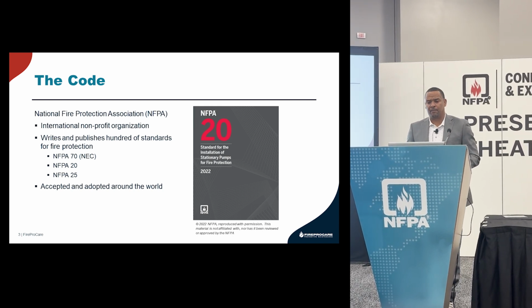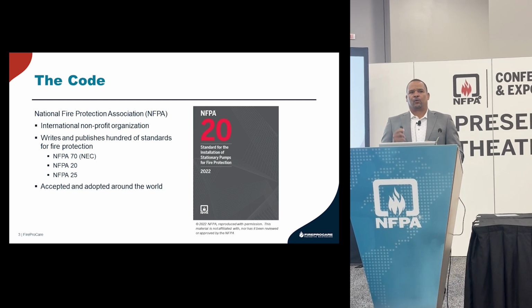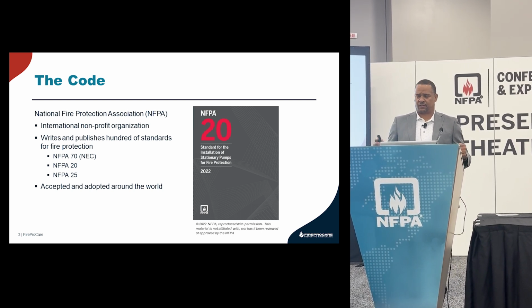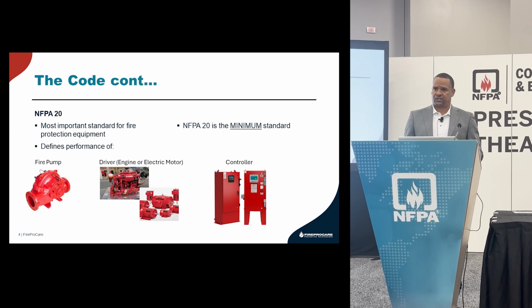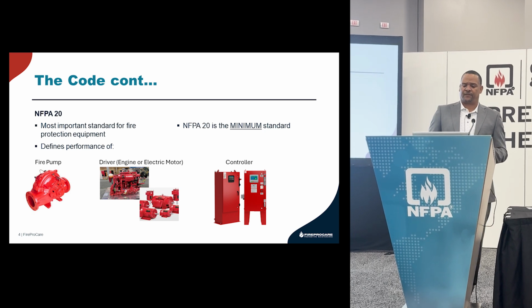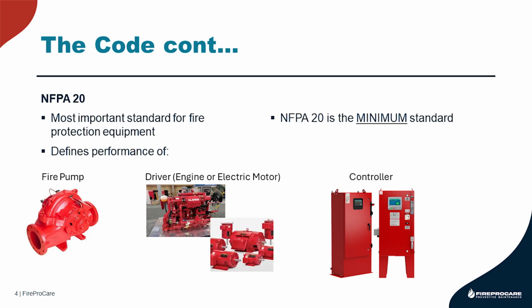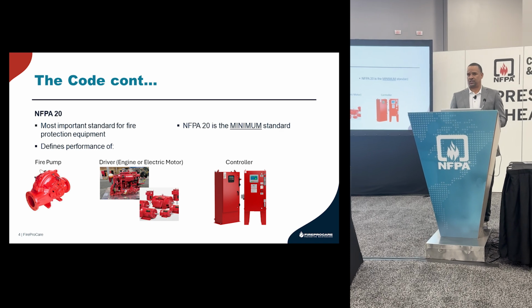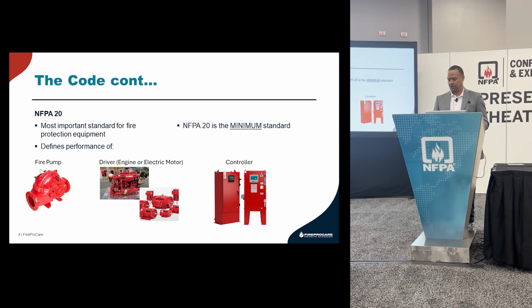NFPA 20 is not necessarily required in every country, but it is the basis for almost every control system or part of the fire pump system. It defines the performance of the fire pump, the driver—whether engine or electric motor—and the operation and design of the fire pump controller itself. It's a minimum standard, meaning your respective areas may go above and beyond NFPA 20, but this gives you the basis of the design. That's why NFPA 20 is so important—it puts everything in one book, and you can usually find the answer to a question in the NFPA 20 manual.